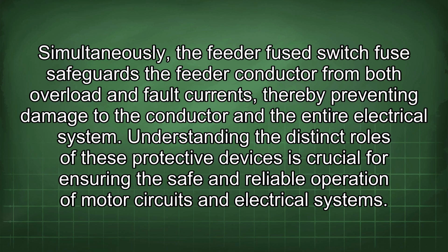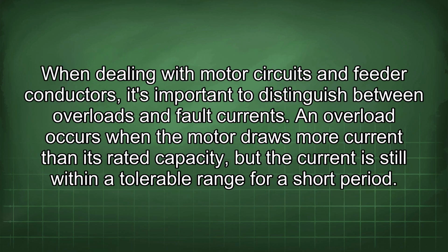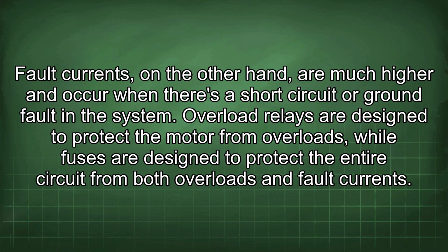When dealing with motor circuits and feeder conductors, it's important to distinguish between overloads and fault currents. An overload occurs when the motor draws more current than its rated capacity, but the current is still within a tolerable range for a short period. Fault currents, on the other hand, are much higher and occur when there's a short circuit or ground fault in the system. Overload relays are designed to protect the motor from overloads, while fuses are designed to protect the entire circuit from both overloads and fault currents.